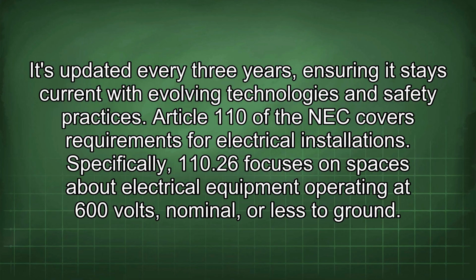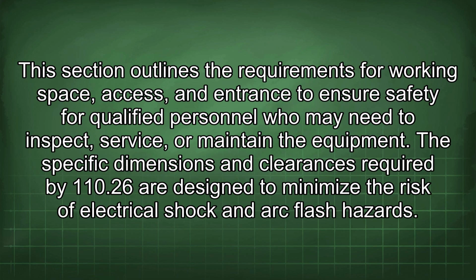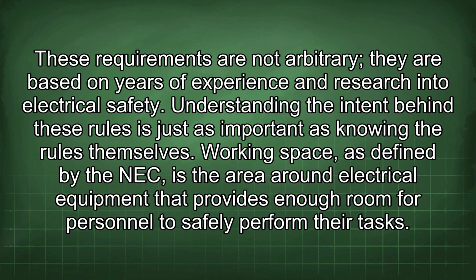Article 110 of the NEC covers requirements for electrical installations. Specifically, 110.26 focuses on spaces about electrical equipment operating at 600 volts, nominal, or less to ground. This section outlines the requirements for working space, access, and entrance to ensure safety for qualified personnel who may need to inspect, service, or maintain the equipment. The specific dimensions and clearances required by 110.26 are designed to minimize the risk of electrical shock and arc flash hazards. These requirements are not arbitrary, they are based on years of experience and research into electrical safety. Understanding the intent behind these rules is just as important as knowing the rules themselves.